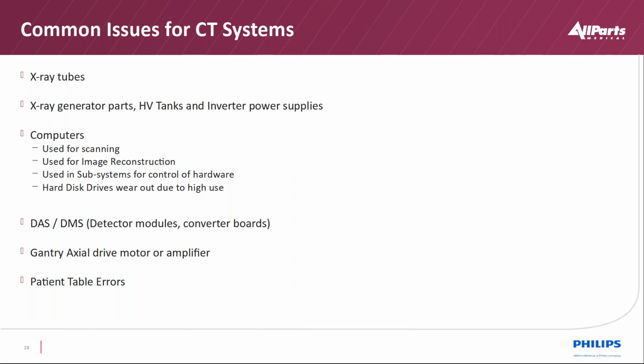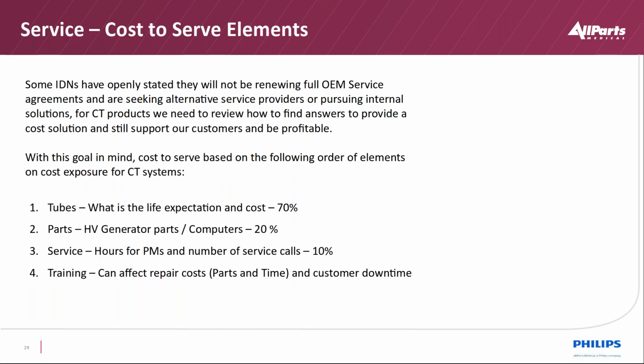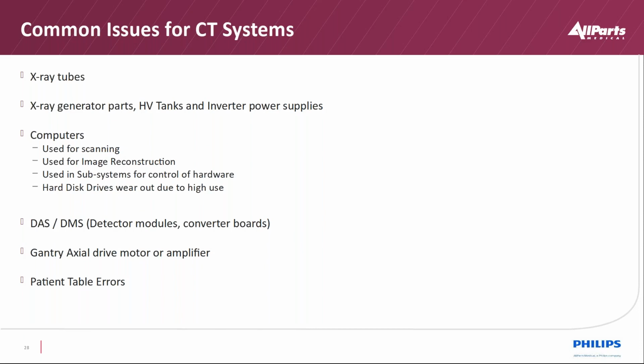Then we have axial drive motors and amplifiers that drive the system. And then we have the patient table where the patient is advanced in. Table errors are very low on the priority list as far as normal failure modes. So we're looking at a hierarchy, from the top all the way down, of the cost to serve a machine from a failure perspective. X-ray tubes don't fail every day; it's the cost that we're looking at in this context. You'll see small errors that might be components that wear out, but from a system and cost perspective, this is the view that we typically see with regards to service costs.